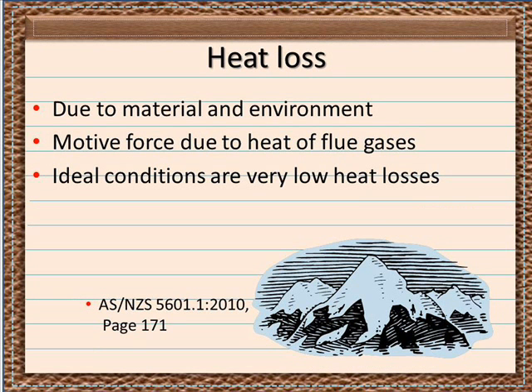When designing appliance flues, heat loss due to the materials and the immediate environment must always be considered. The heat of the flue gases causes them to move up the flue — any heat loss causes the flue gases to slow down. If sufficient heat is removed from the flue gases, its temperature may drop below the dew point and condensation may begin to form.